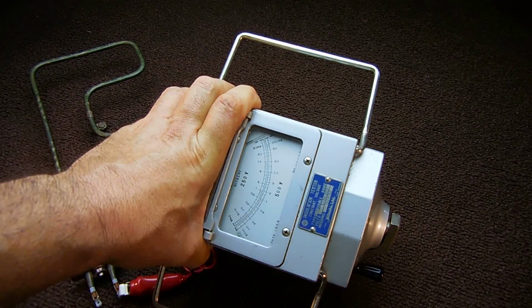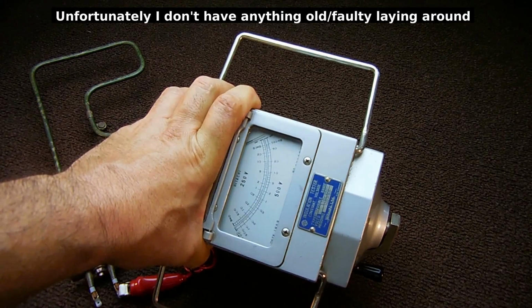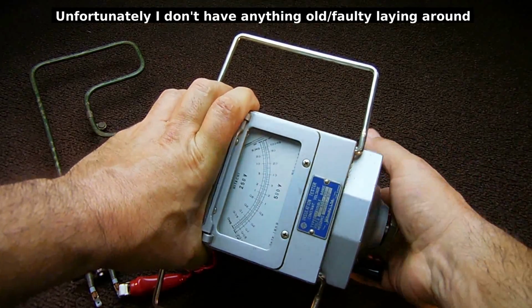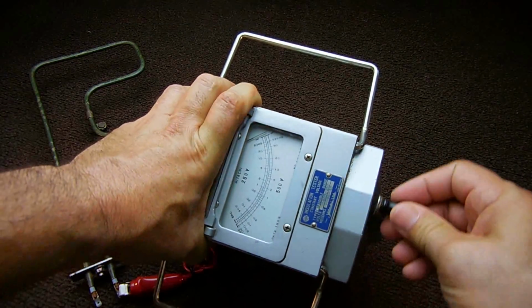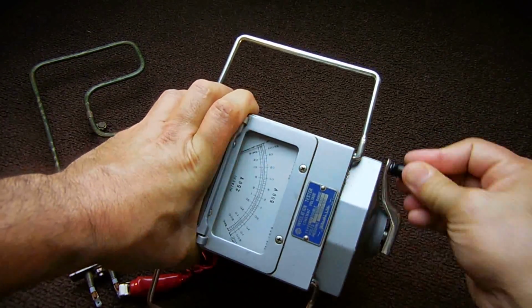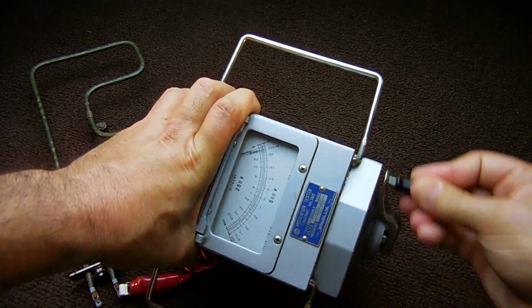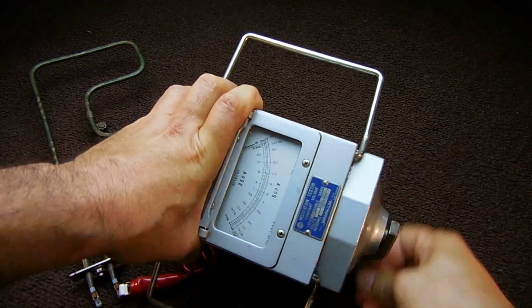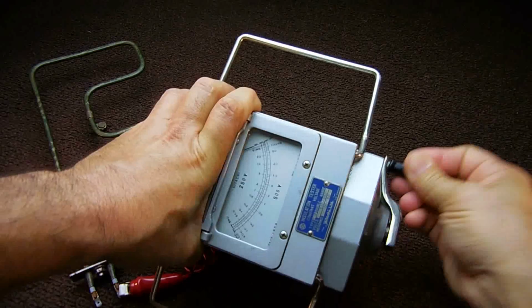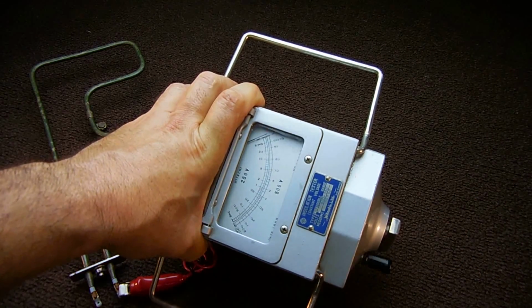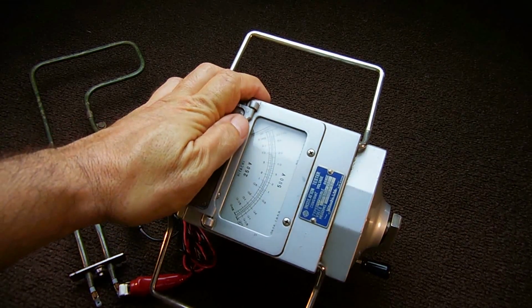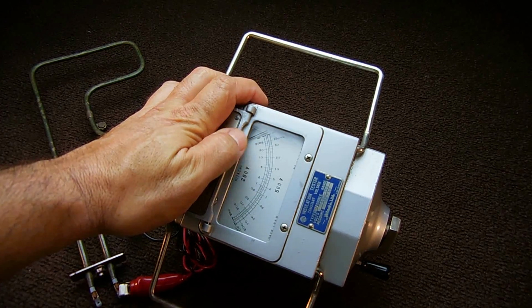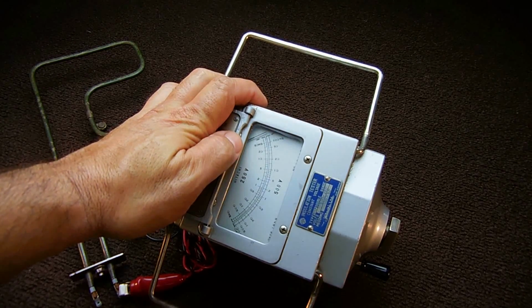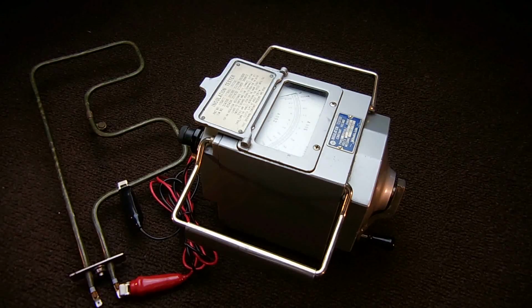And you can see there's not much going on with that one. It is a fairly new element. Let's put this to 500 now, see what happens. And you can see the 500 did cause a little bit of breakdown, but it was still well above the 100 megohm range, probably a couple of hundred megohm. Shortly I'm going to be repeating these tests using the electronic unit.